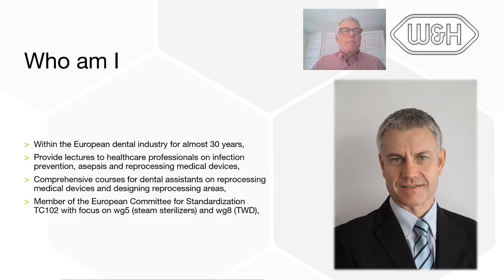I'm also a member of the European Committee for Standardization since 1997. I'm following two working groups on TC102. Working group 5 regards small steam and big steam sterilizers, and working group 8 concerns thermal washer disinfectors. I had the privilege to co-design and co-develop a high-end B-type sterilizer. This was before the year 2000.